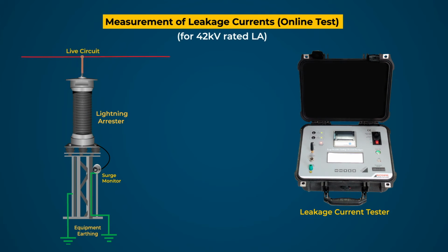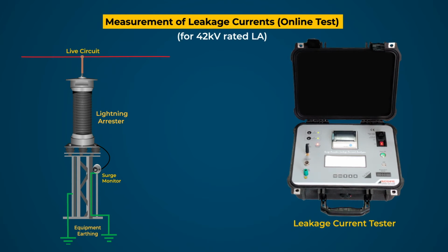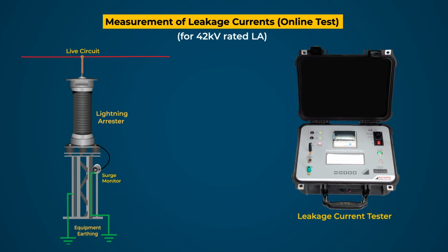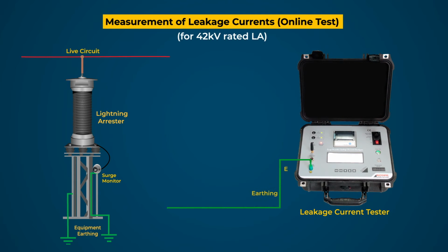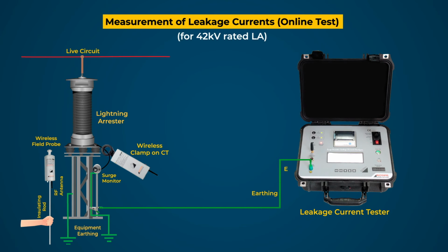Steps for testing. This test method is based on the third-order harmonic analysis with voltage harmonics compensation. Test kit is battery-operated and has a clamp on CT and a field probe. Connect the master earthing of the test kit to the earthing of LA. After this, clamp the wireless clamp on CT in a cable connecting the bottom of LA to earthing through surge monitor. Remember to connect the clamp on CT before the surge monitor. One person shall hold a wireless field probe that is connected to the insulating rod and stand under LA and place the field probe near LA bottom part, taking all precautions.